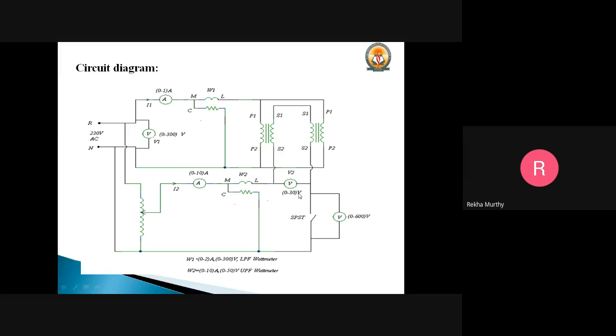The voltmeter of range 0 to 600 volts is connected here. An SPST switch is connected in between. When the SPST switch is open, the open circuit test is conducted to find the core loss. When the SPST switch is closed, the short circuit test is conducted. We also need to connect a voltmeter across the SPST switch. The primary of the second transformer is also connected back to back — P1 and P2 are connected back to back. We need to combine the two circuits, that is the OC test and short circuit test circuits.